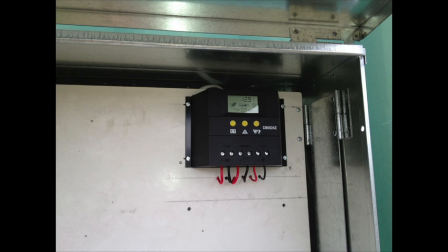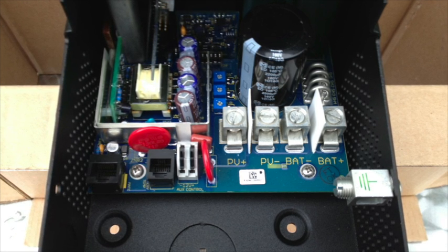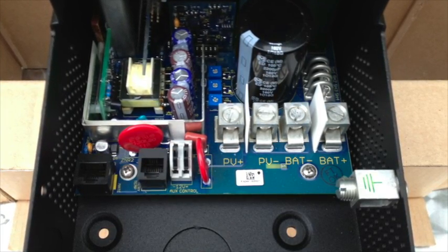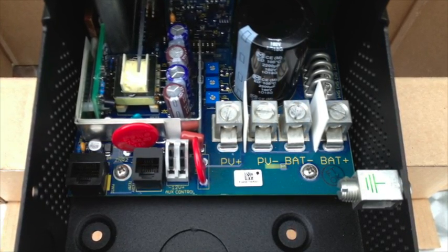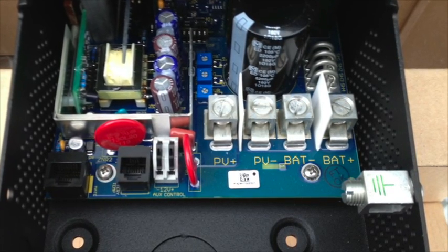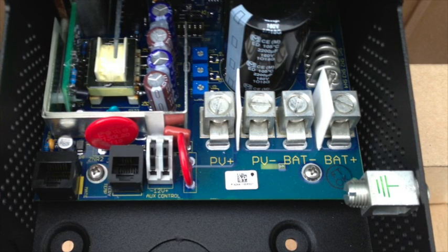So what you do is you have a string on this side and you have a string on this side. Cheap charge controllers can generally only handle small size strings. And they're usually not very efficient. A better quality has something called MPPT, which is maximum power point tracking, which gets a lot more of the electricity into the batteries from the solar panels. They're more efficient. You normally need a better quality unit to be able to handle two different strings by itself.